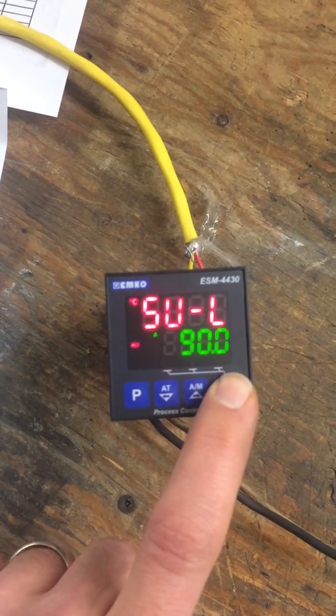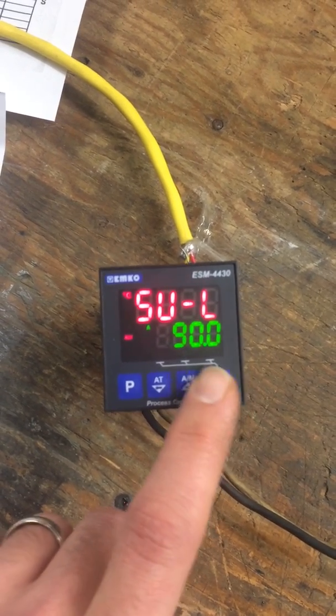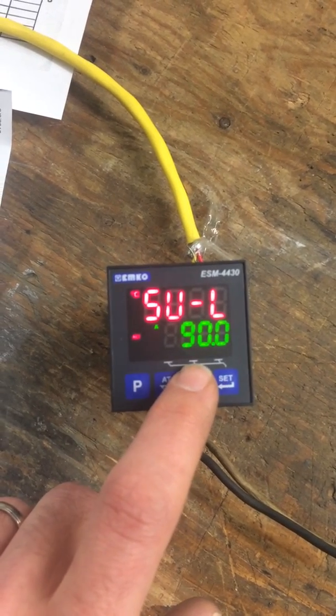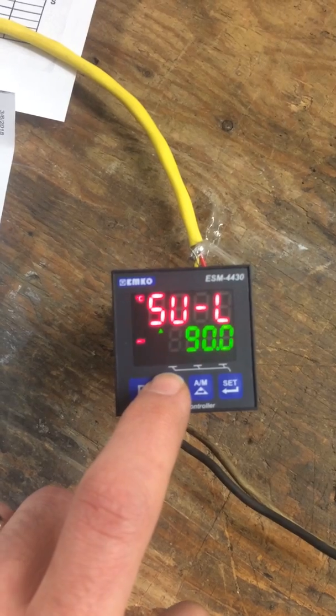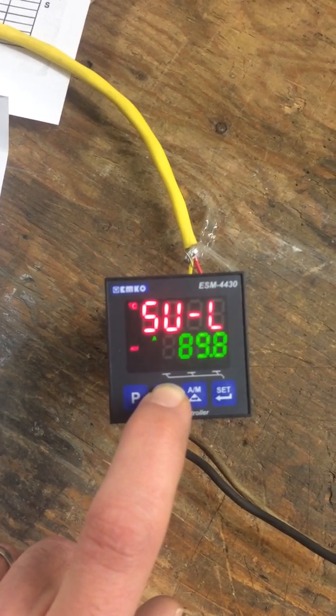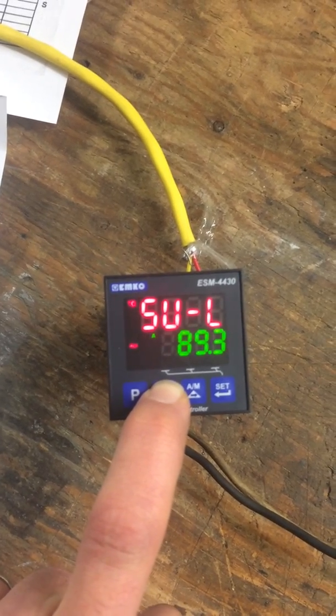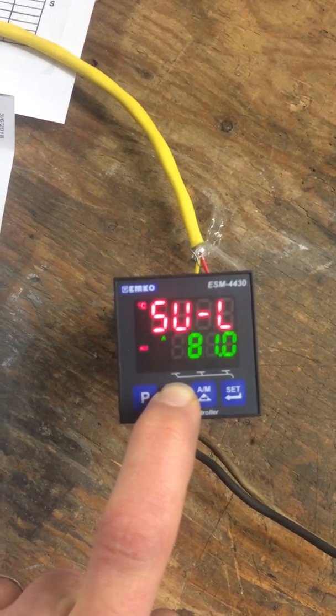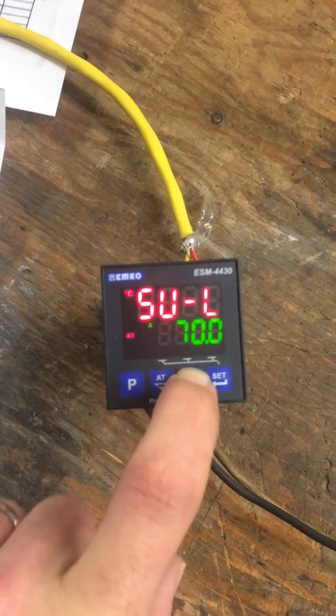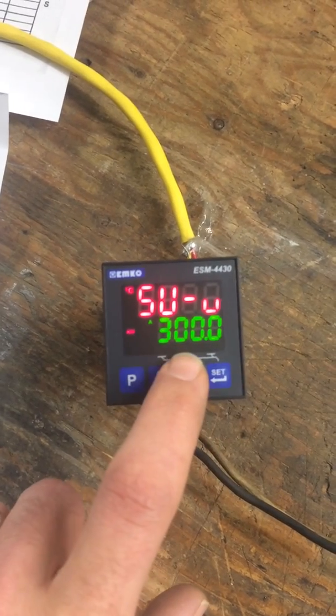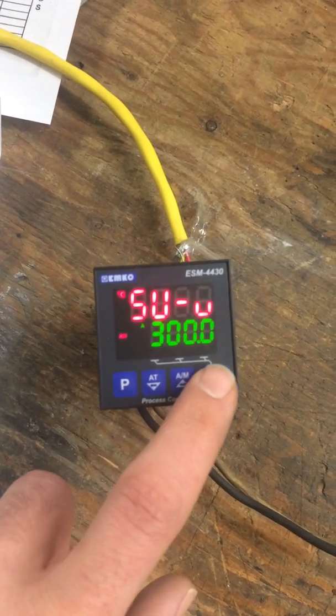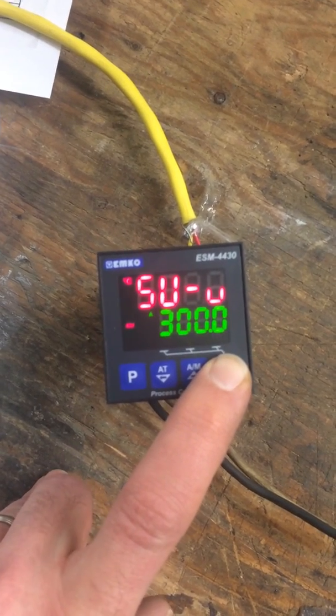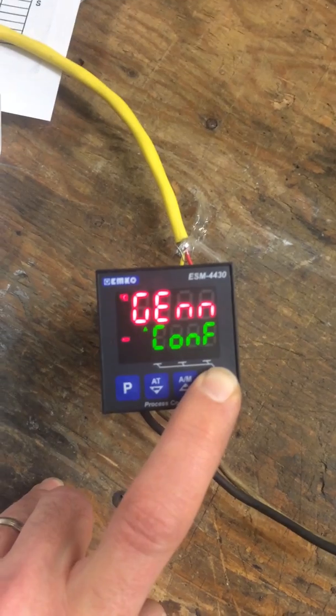The general configuration: the only thing we're going to do here is look at this. It doesn't matter as long as the variables are set to that previous range. Basically, you give your customer the option of where he wants to set it. Usually I put it like 70°C on low, with your maximum at 300, which is what we're set to as the maximum temperature — 600 Fahrenheit. That's a critical alarm. Exit out of these, back to the main.